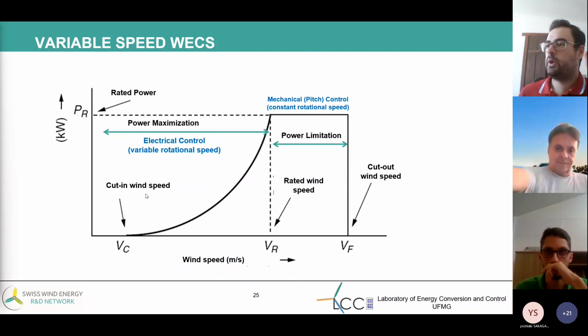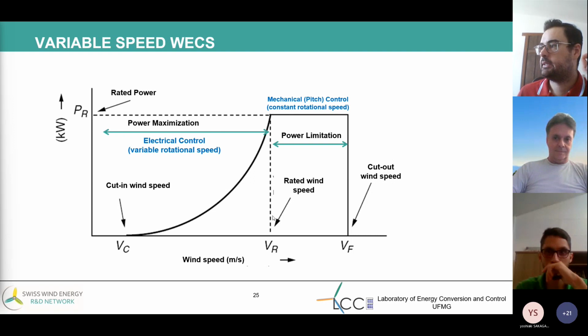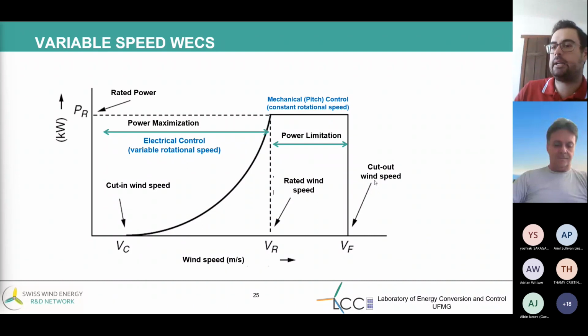Between the cut-in speed and the rated speed, we have electrical control, power maximization. Between the rated speed and the cut-out wind speed, we have the power limitation, with the pitch control. Above the cut-out wind speed, the speeds are very high, for example, a tornado or a hurricane, that can damage the turbine and the blades, and then the system is turned off. It's a kind of protection of the system. Even above the rated wind speed we can operate, but with the limitation done by the pitch angles.